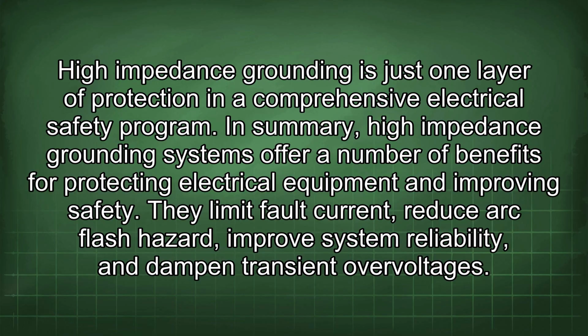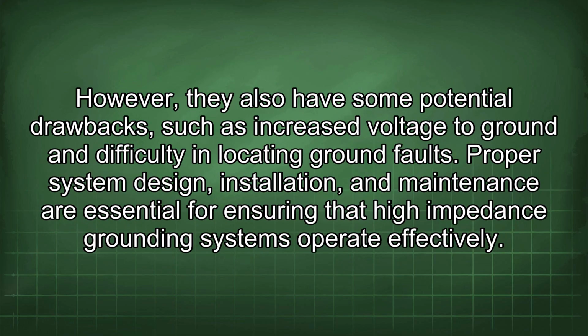In summary, high-impedance grounding systems offer a number of benefits for protecting electrical equipment and improving safety. They limit fault current, reduce arc flash hazard, improve system reliability, and dampen transient overvoltages. However, they also have some potential drawbacks, such as increased voltage to ground and difficulty in locating ground faults.